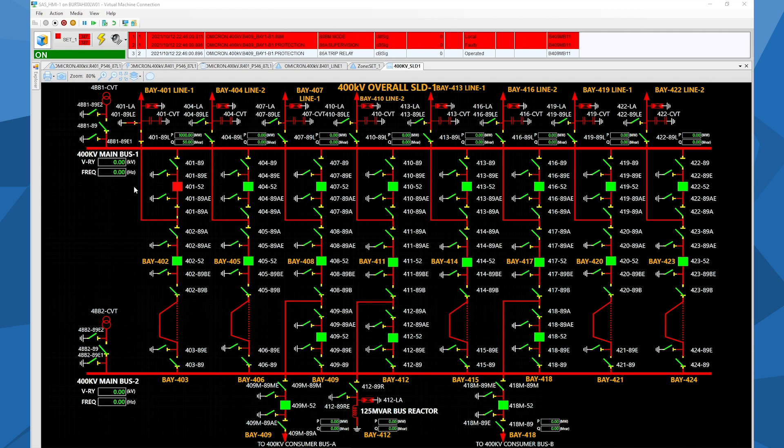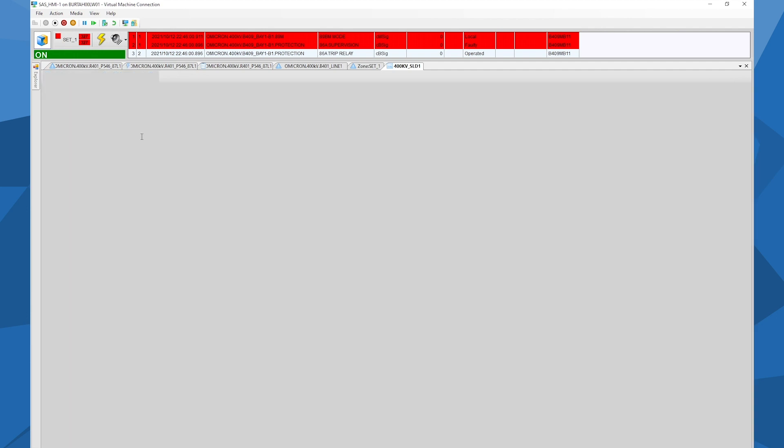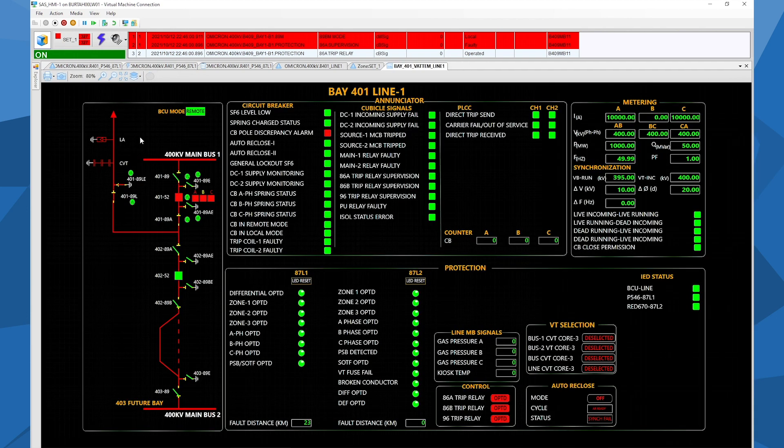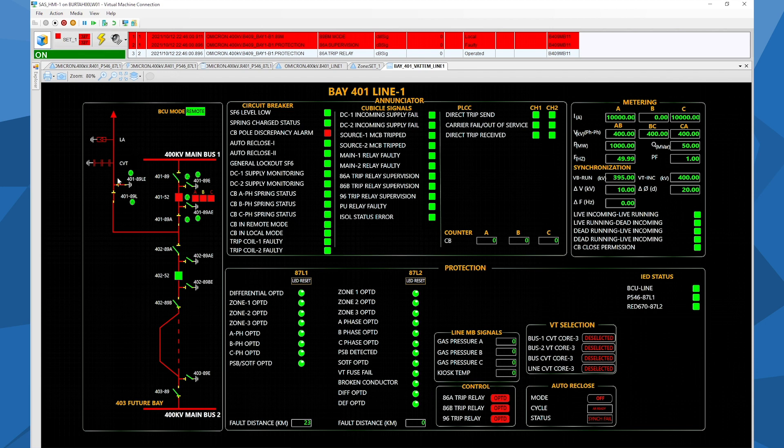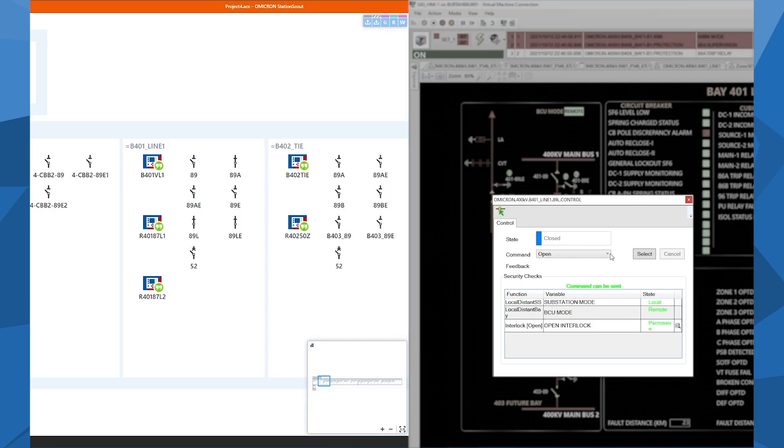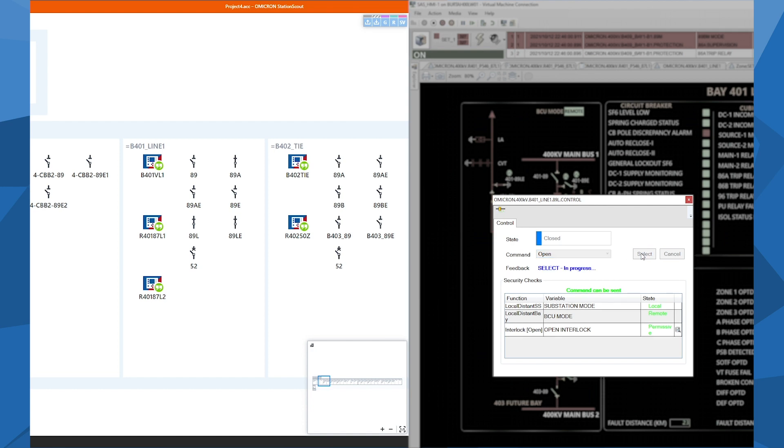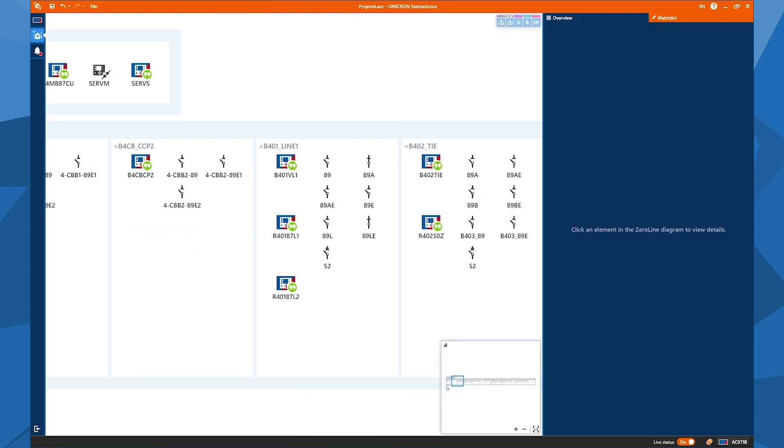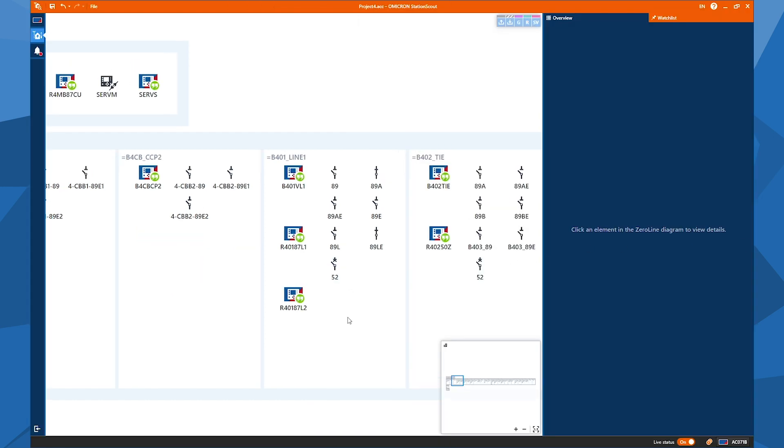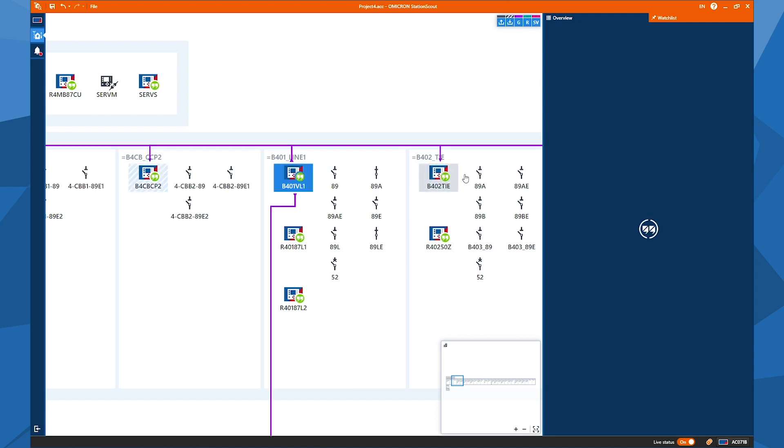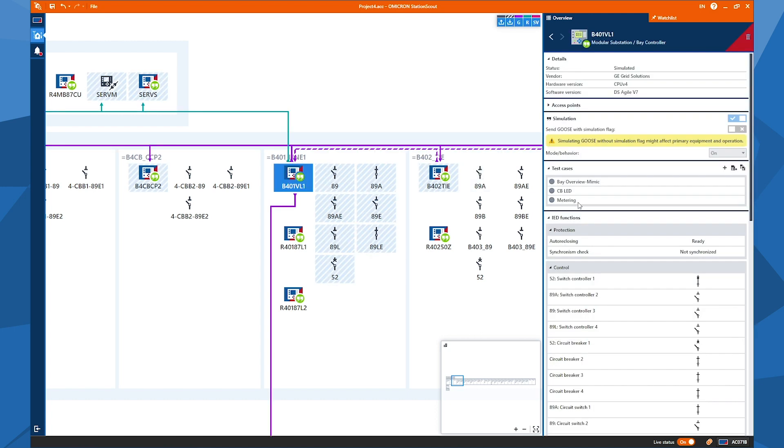I can also check this connector, for example. I can send a command from this connector to the Station Scout. So for doing that, I click on this connector and I select it. So when I click on operate, you will see that 89L will be opened. Okay, so it will be, it's open now. Okay, with this way we can test all the positions, and I prepared the test case to test this.